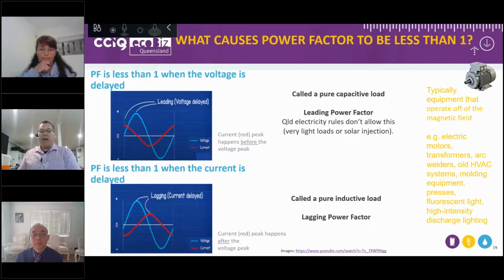Leading power factor is something that the Queensland electricity rules do not allow for. Any customer that is causing a leading power factor and feeding VARs back into the grid is not allowed under the rules. When identified, we actively try to work with that customer to identify what the issue may be and how it can be fixed.